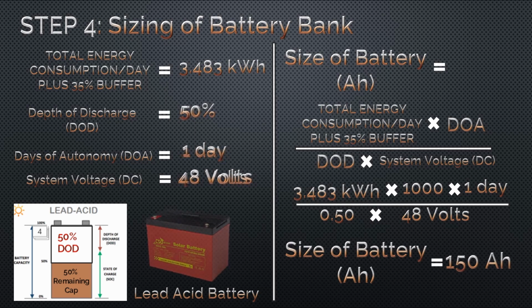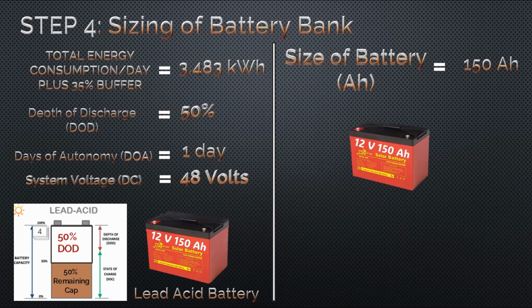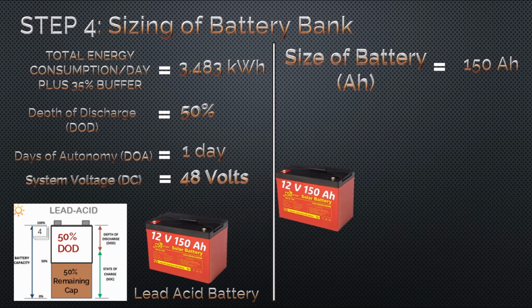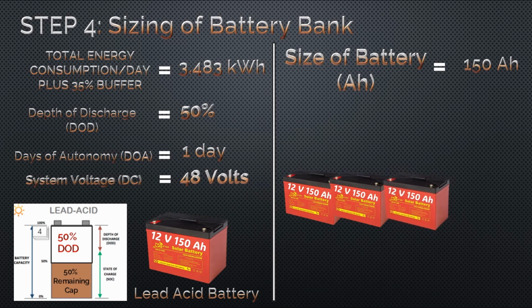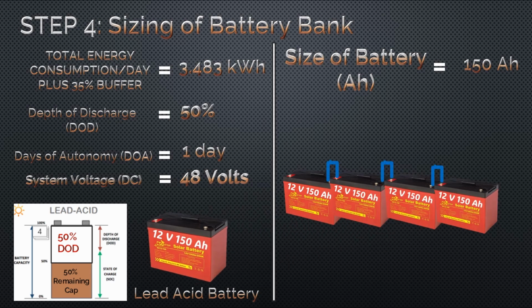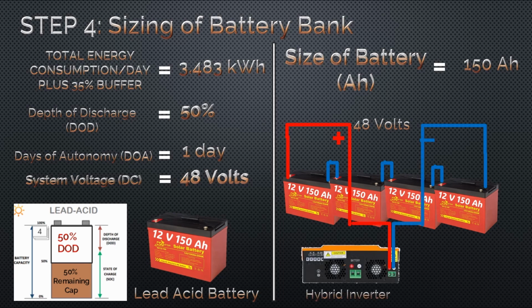So the 150 ampere hour we get is the capacity of a 12 volt 150 ampere hour battery. But our DC system voltage is 48 volts. So we need 4 batteries, and the 4 batteries will be connected in series to get a 48 volt battery bank. Then the positive and negative terminals of the battery bank will be connected to the inverter. Since you chose a 48 volt DC system, it is necessary to buy an inverter with 48 volts DC input voltage.